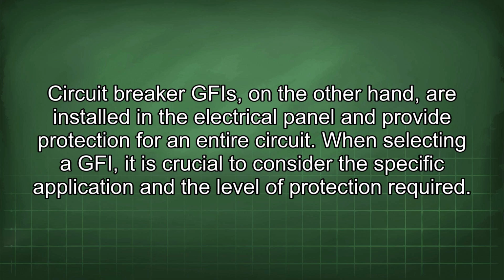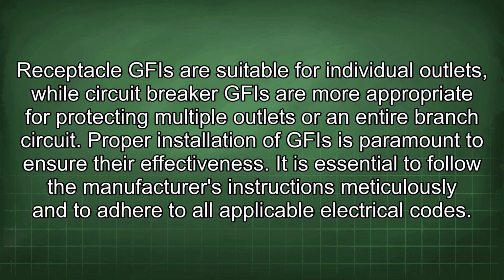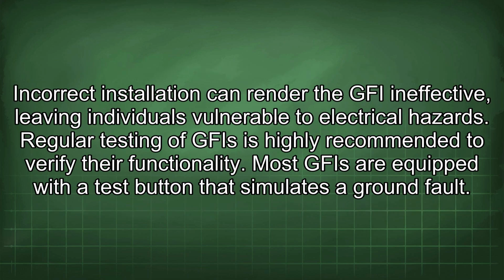When selecting a GFI, it is crucial to consider the specific application and the level of protection required. Receptacle GFI are suitable for individual outlets, while circuit breaker GFI are more appropriate for protecting multiple outlets or an entire branch circuit. Proper installation of GFI is paramount to ensure their effectiveness. It is essential to follow the manufacturer's instructions meticulously and to adhere to all applicable electrical codes. An incorrect installation can render the GFI ineffective, leaving individuals vulnerable to electrical hazards.